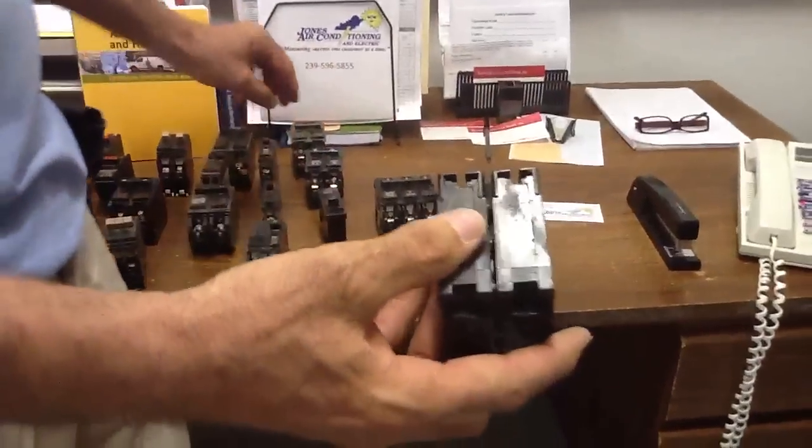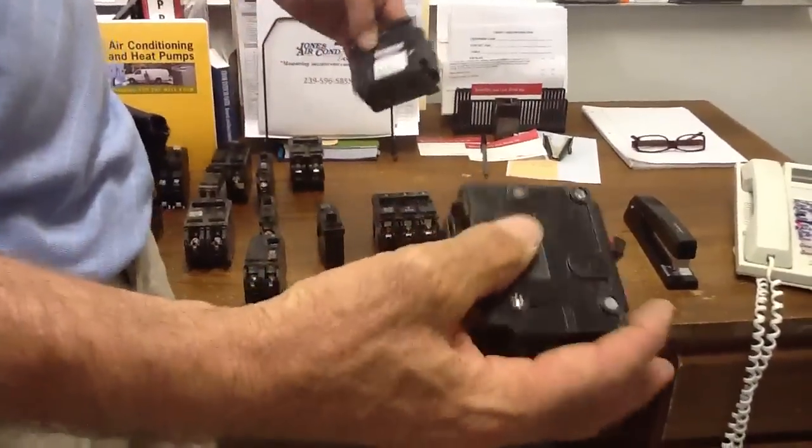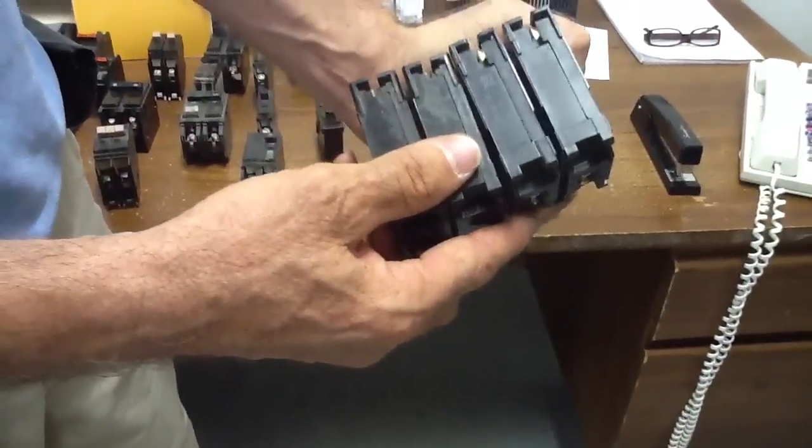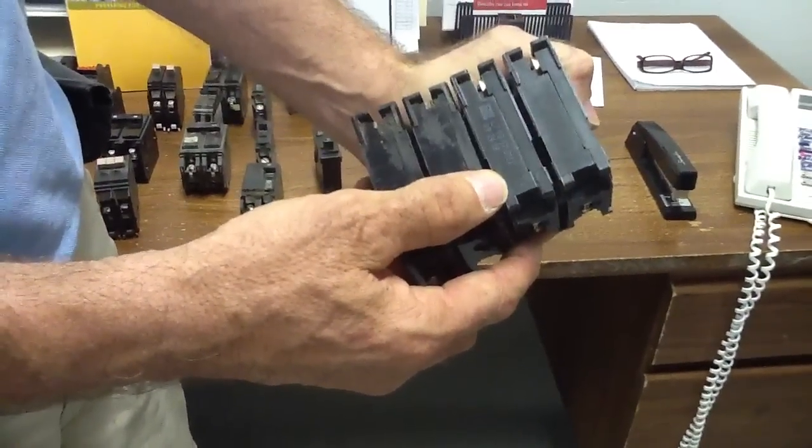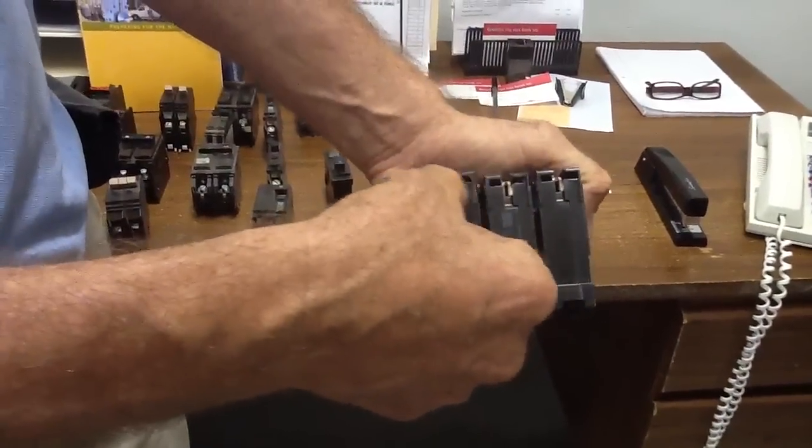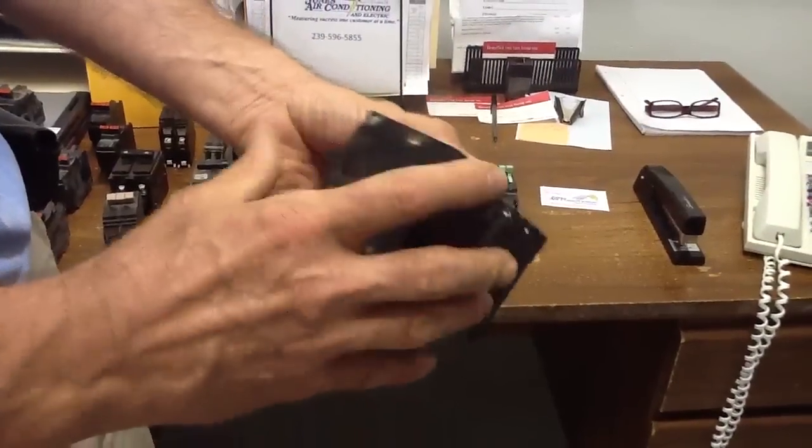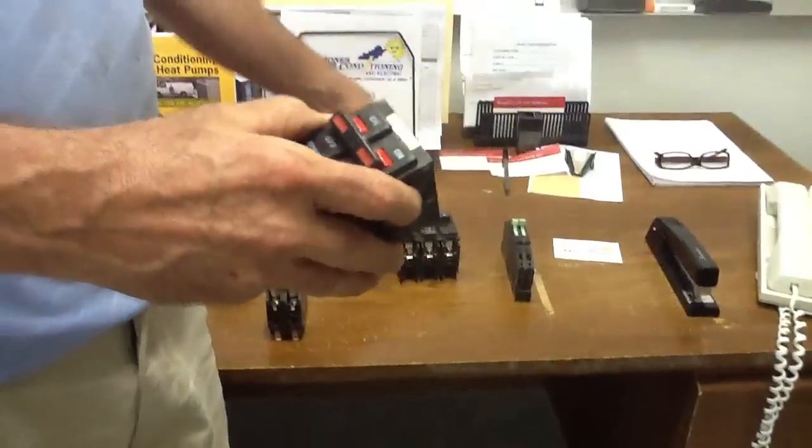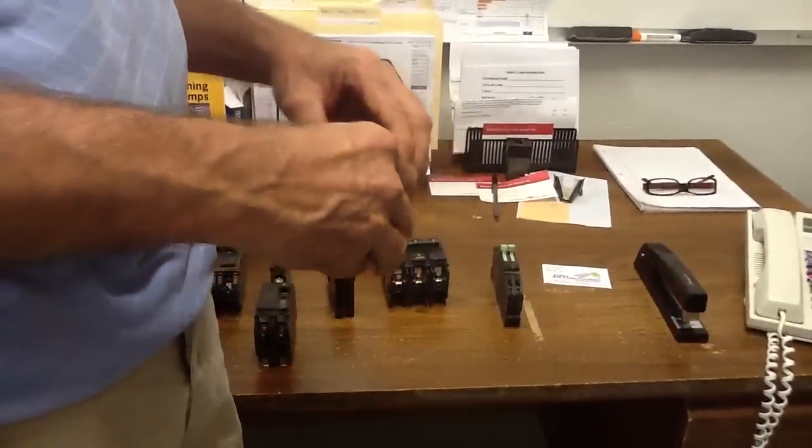Once again, this is a double pole. This is an old breaker, is what this is. I pulled out of somebody's. See the footprint? The footprints are the same. So yes, you could interchange these breakers if you wanted to, but you're not supposed to. A qualified electrical contractor would know better, and he wouldn't do it. That's why it's always important to use licensed contractors in your business.